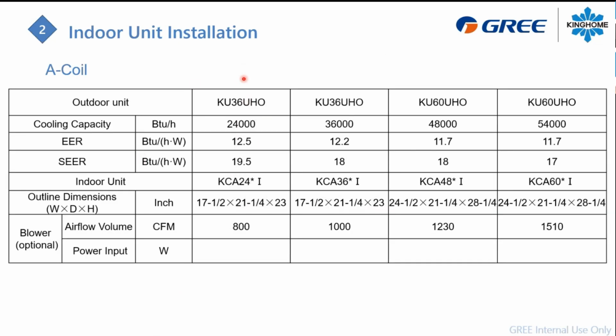So this is like if you fit the case coil here, the 2 ton with a 3 ton unit, because we're going to see it later on, but we have only 2 different kinds of outdoor unit. One that can be selected as a 2 ton or a 3 ton, and the other one as a 4 ton or a 5 ton unit. But if we're talking about just a 2 ton installation, you can have a different CFM that is the minimum recommended through that type of case coil.